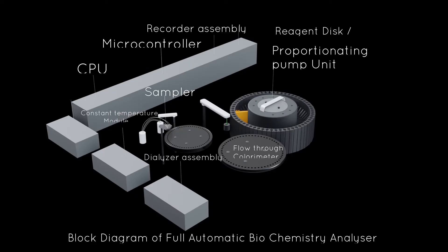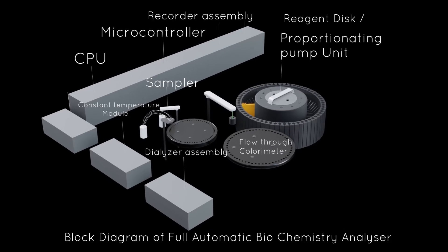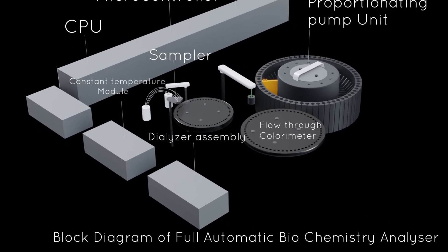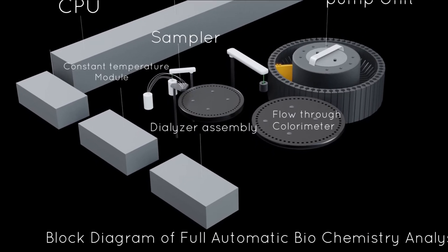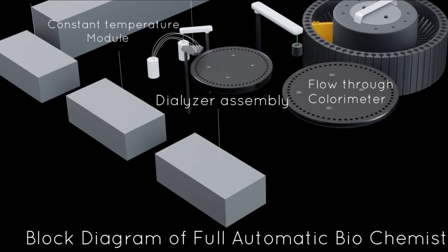The next component is the dialyzer assembly. This module achieves the separation of small and large molecules by allowing the former to pass through a semi-permeable membrane from the donor or sample stream of liquid and air bubbles to a recipient stream of liquid again segmented by air bubbles.